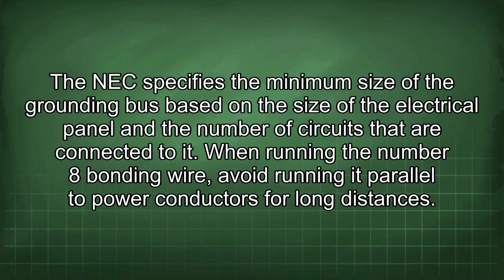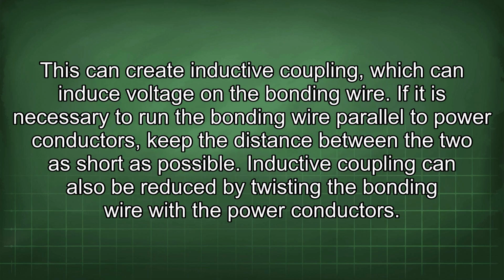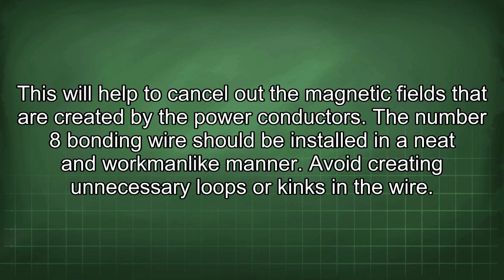When running the number 8 bonding wire, avoid running it parallel to power conductors for long distances. This can create inductive coupling, which can induce voltage on the bonding wire. If it is necessary to run the bonding wire parallel to power conductors, keep the distance between the two as short as possible. Inductive coupling can also be reduced by twisting the bonding wire with the power conductors. This will help to cancel out the magnetic fields that are created by the power conductors.